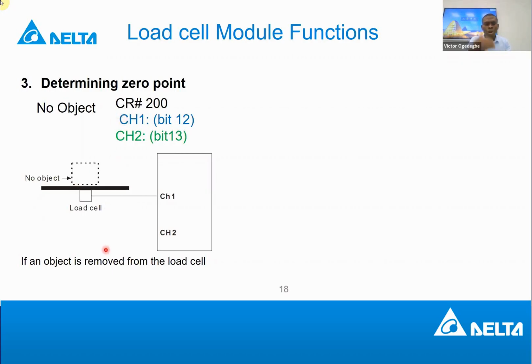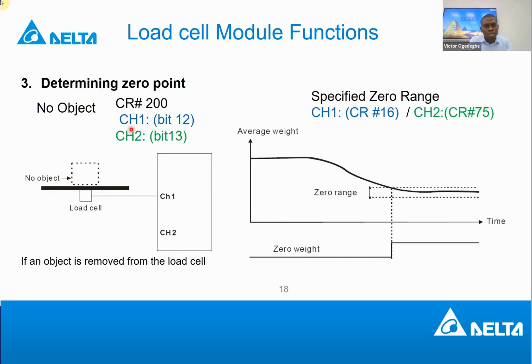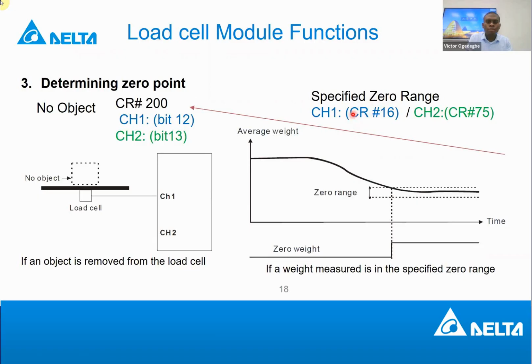And also, this one is more advanced. It's also possible that besides no weight, you want to specify by yourself a 0 range. So for channel 1, this is control register 16. In this control register, you want to set a digital value, that if the sensor is measuring and I read this value, I want to set this value as my 0 range. In real sense, it's not 0, but you are choosing to make it 0. So you have specified it as 0 range. So what happens is that when the weight measured gets to that point, the bit is also triggered for channel 1. This bit 12 also reacts to it.